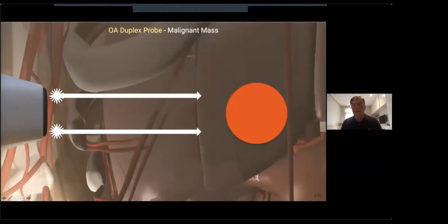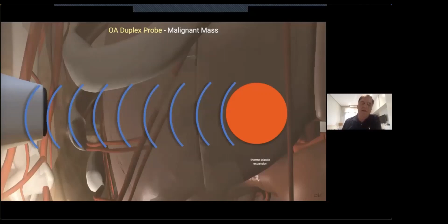How long does that take? 200 microseconds. Obviously, it's going to be a little longer for deeper, a little less for more superficial lesions, but on the average, 200 microseconds. And we fire 10 pulses per second, but 5 is the short wavelength, 5 is the long wavelength. So since you need both a long and a short to create a single frame of OA, the actual update rate of OA is 5 frames a second.